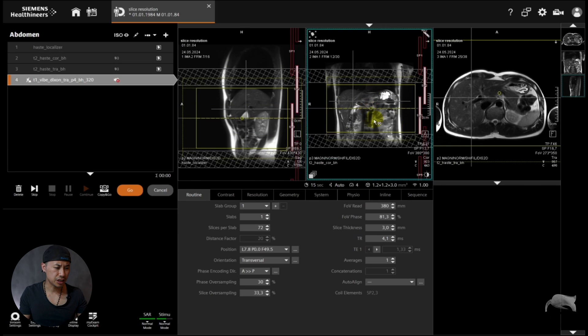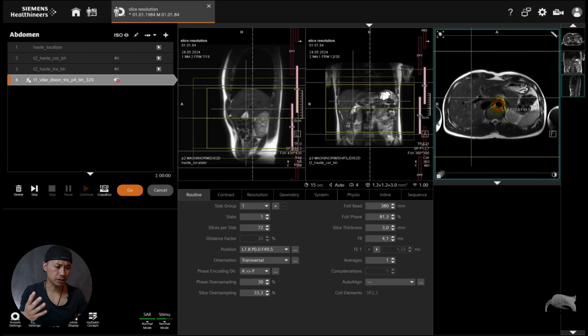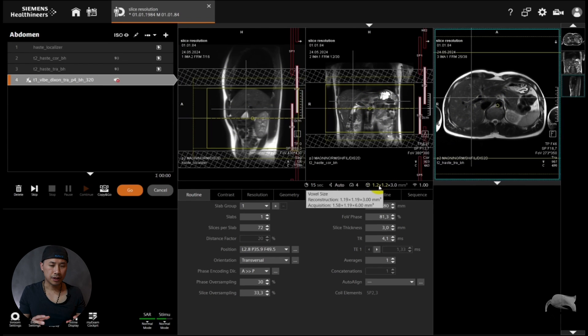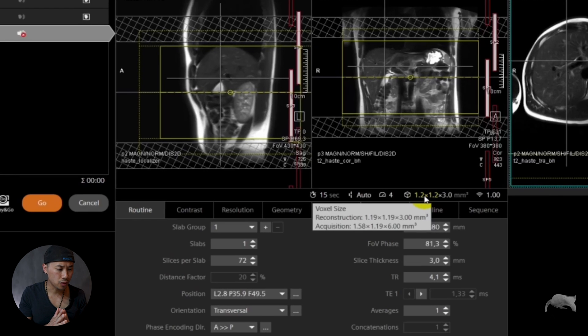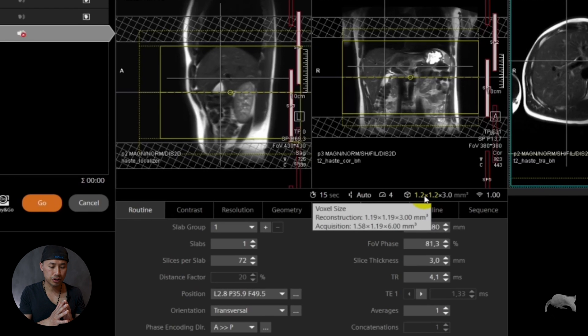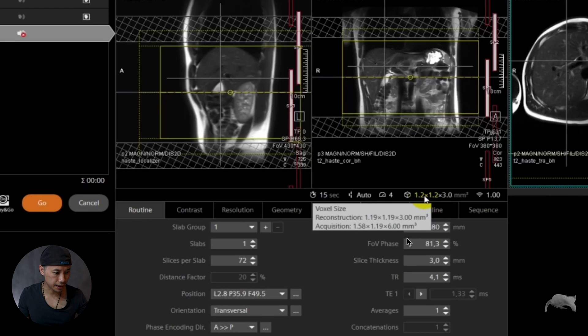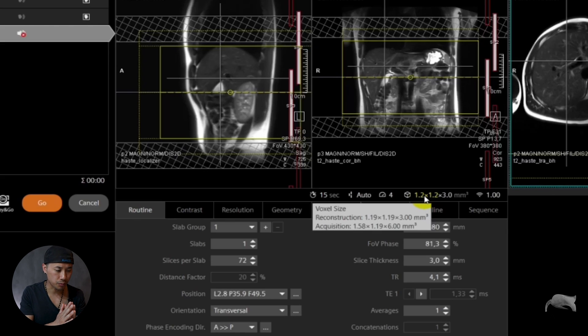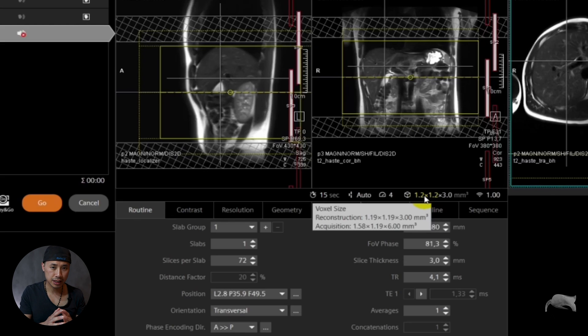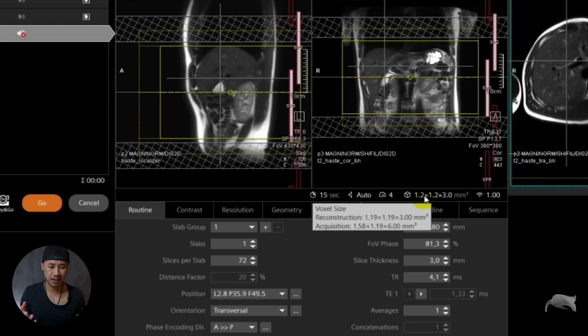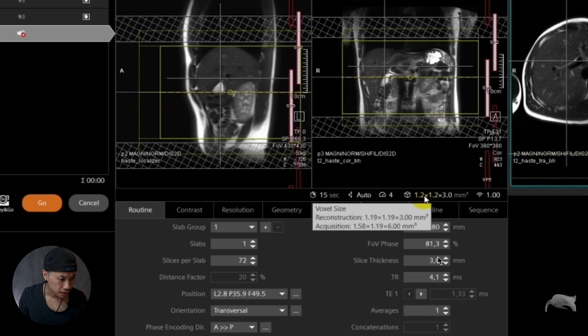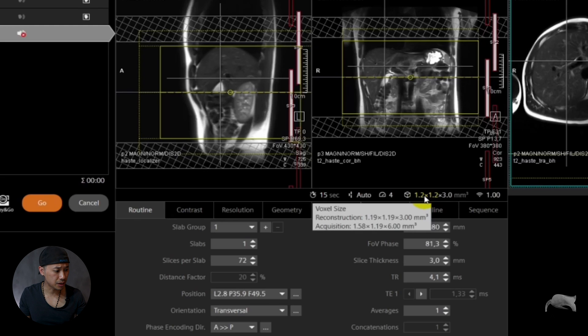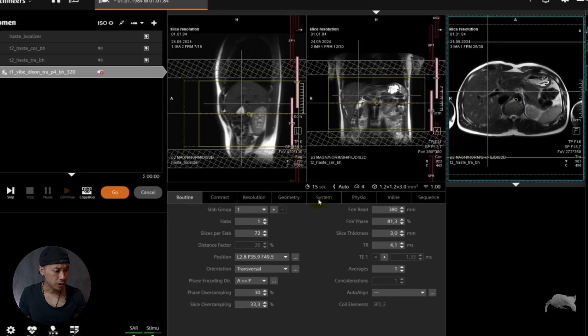Just try to tune in the position even though I'm not going to run the sequence. If we hover over the resolution up in the right corner, as you can see here, you have your mouse over here. Then you can see the acquisition is now for the phase 1.58, frequency 1.19, and then the slice is 6. How come the slice thickness be 6 when it says here 3 millimeter? Well that's what I'm about to show you.